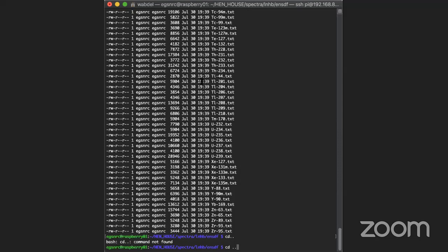Then calculate your phase space file and analyze it to get the spectrum, because then you can modify the filtration or the energy of the electrons. The thing to look at carefully is the thickness of these filtrations.